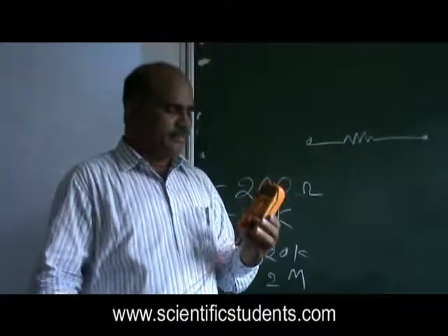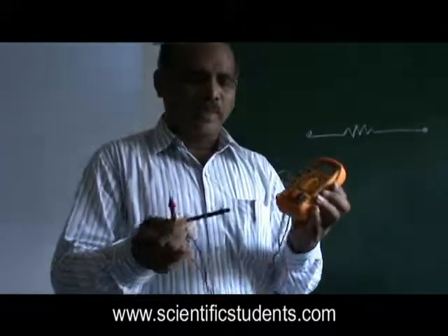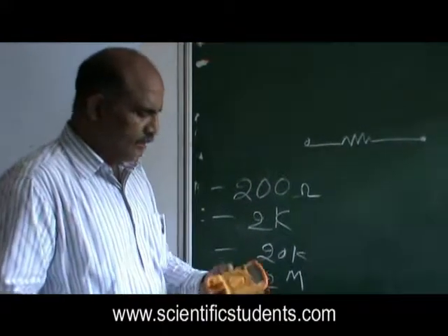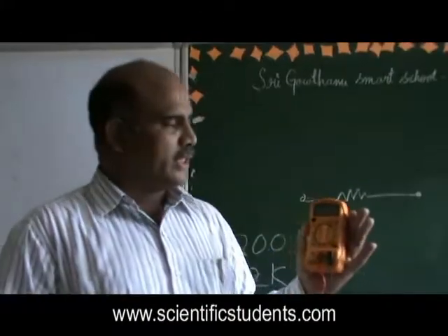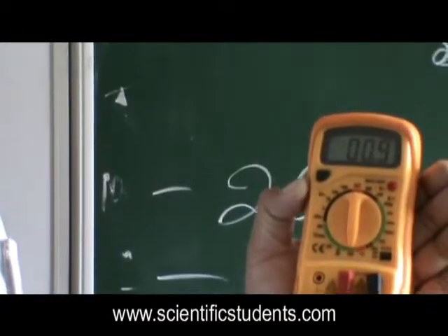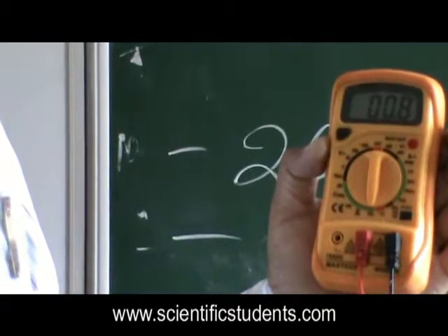Okay, and also to make sure your cables are connected properly, or inserted properly, and the contacts are also perfectly alright or not, to check all this, what do you need to do? You always go on the low range, like 200. Okay, keep it low, and then short circuit these two, and make sure this is 0. Now it is showing 0.9, 0.8. It is trying to self-calibrate.